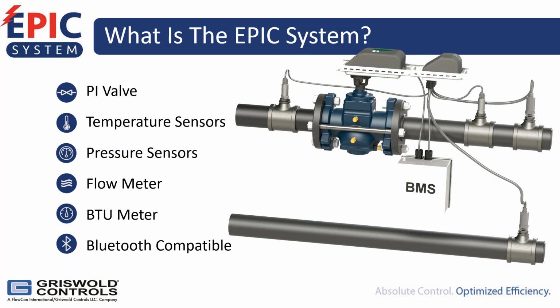And as we know, hydronic systems are constantly experiencing pressure changes as the different zones in the building are having different loads that are changing the load requirement, and as the rooms in the building are experiencing a change throughout the day, that will cause a system pressure change anytime there's a control valve change. And so the pressure-independent valve is the heart of the EPIC system.